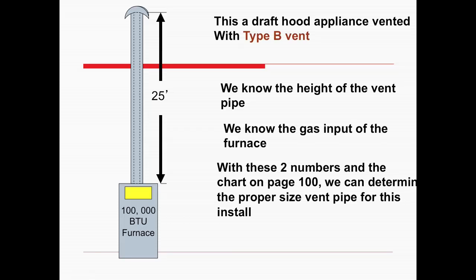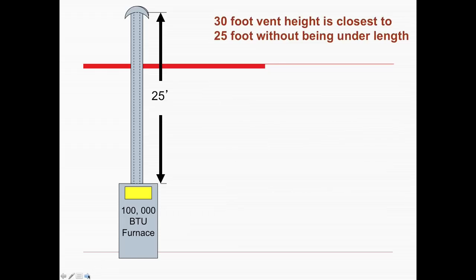We know the gas input to the appliance. We can go to the chart on page 100 and determine the proper vent size. This is done with the 2012 IFGC International Fuel Gas Code — later editions will probably have a different page number. A 30-foot vent height is the closest to 25 feet without being under length, so it has to be at least that long or the next one up.